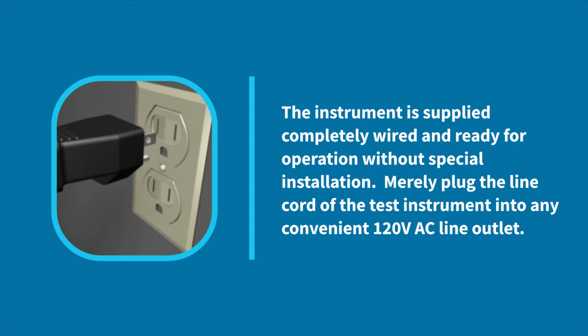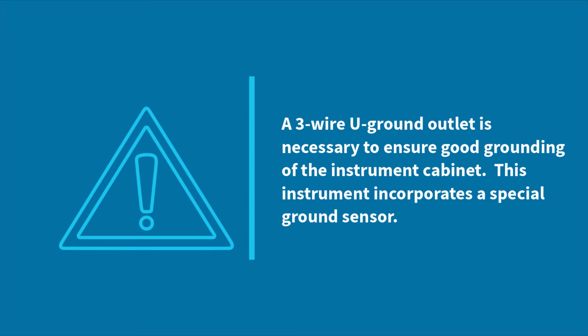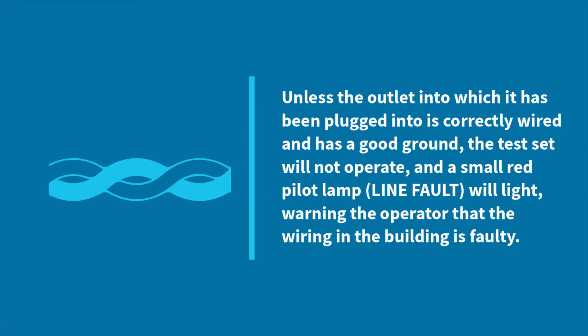Merely plug in the line cord of the test instrument into any convenient 120 volt AC line outlet. A 3-wire U-ground outlet is necessary to ensure good grounding of the instrument cabinet. This instrument incorporates a special ground sensor. Unless the outlet into which it has been plugged is correctly wired and has a good ground, the test set will not operate, and a small red pilot lamp, line fault, will light, warning the operator that the wiring in the building is faulty.